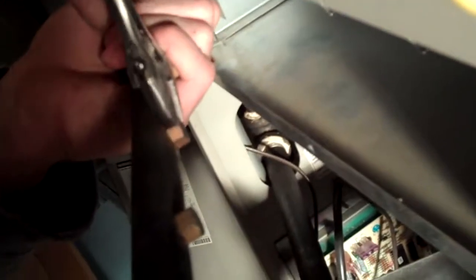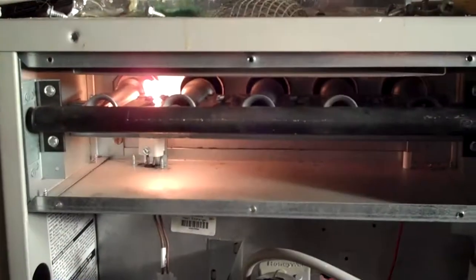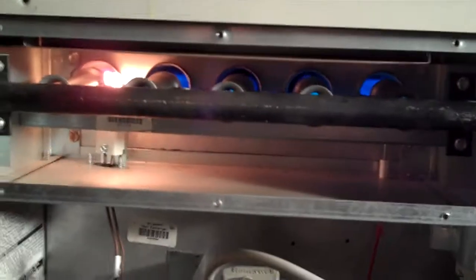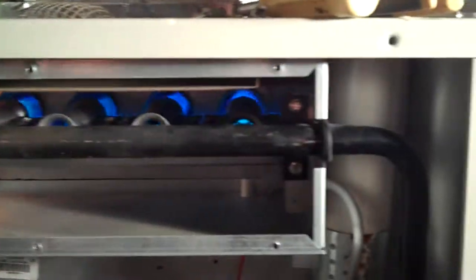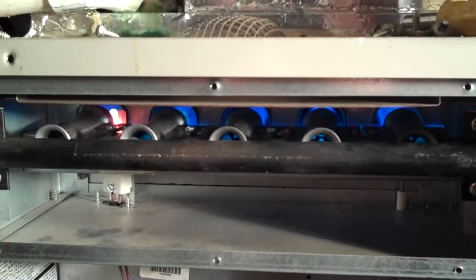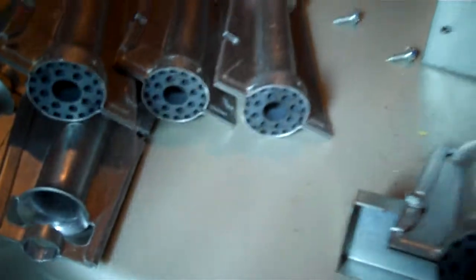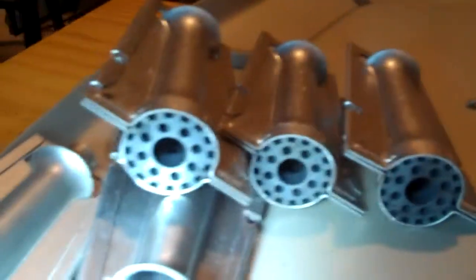I've never seen one of these plug out. Now today, believe it or not, we're changing the burners on the Nordyne furnace. It's propane, and you'll see where the little jumpers are in between each of the burners, all corroded, and that one there in particular. So what was happening is only half of them were firing and then it shut off. It wouldn't sense the flame. So we're just going to change them all.